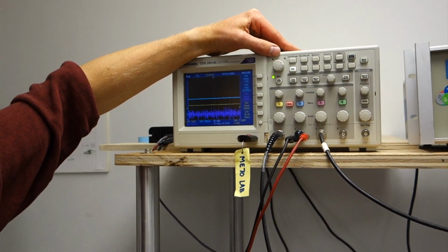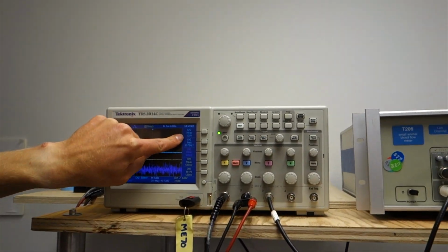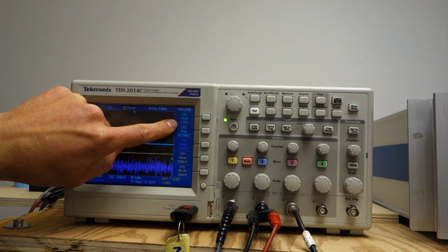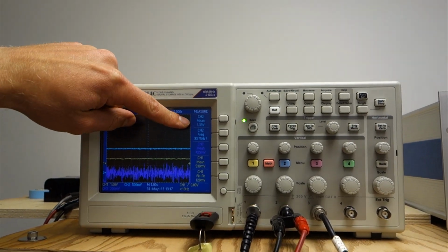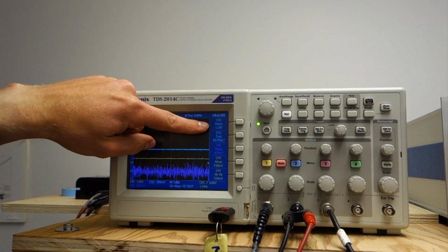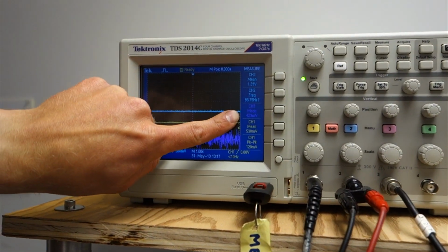Okay, ready? Okay, so we've measured channel 2. The voltage pressure is 1.39 volts, so I will convert that into millimeters of mercury using our transfer function for the pressure sensor. And then we'll do the same thing for channel 3, the purple. We have its 429 millivolts.